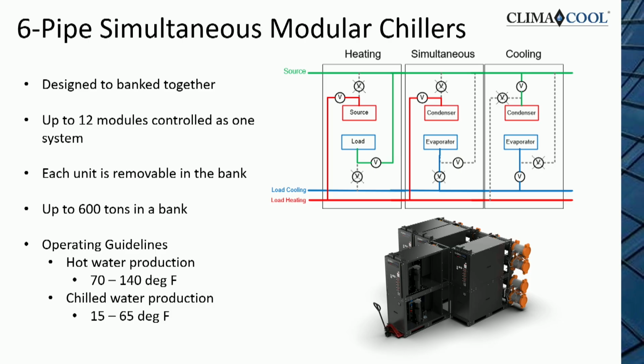But the beauty of this technology, again, is it's simple. It goes through a doorway. It's light. You have replacement options if you want to keep a unit on site for replacement. All of these units can be easily pulled out and serviced if need be. And really, each module does not necessarily care what the other module is doing. Now, that's not necessarily saying you're going to run it that way, but in reality, since we're only mixing on the water side, the refrigeration system is very simple.